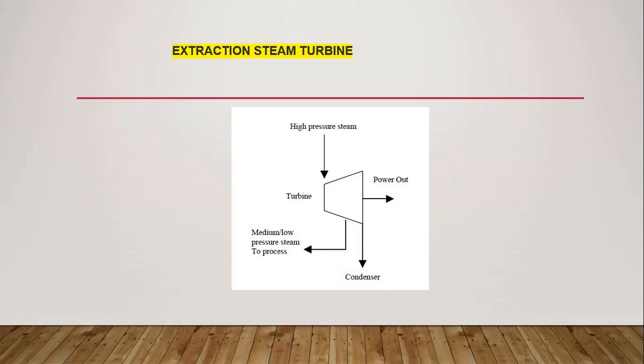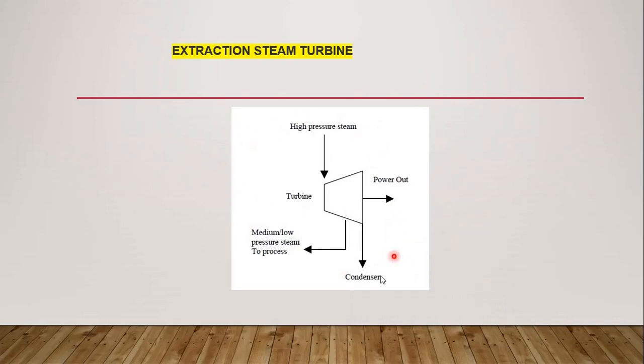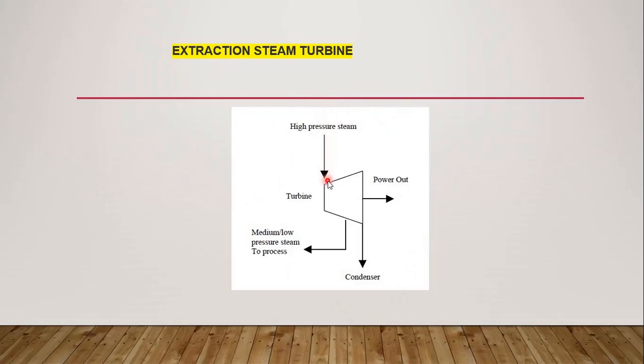In this picture here, with a laser pointer, you can see this is the extraction steam turbine design. What happens here is that this turbine basically contains two outlets. The steam comes in, but steam goes out from two ways — one is going to the condenser and one is going to the process. Steam is coming inside, it is rotating the blades, the turbine is rotating. One outlet connects with the condenser, another outlet is the extraction of low pressure steam to the process. This type of design is called the extraction steam turbine — one inlet and two outlets.